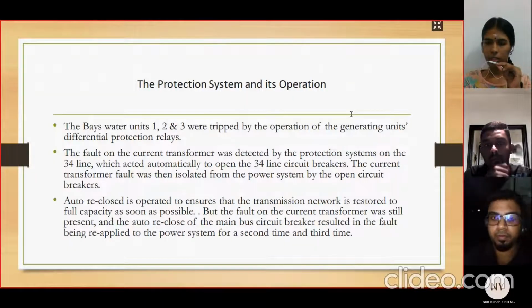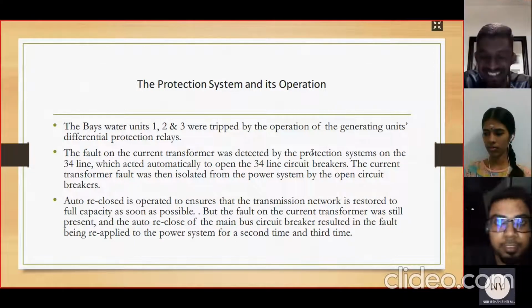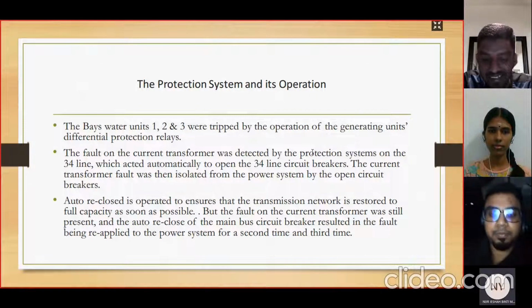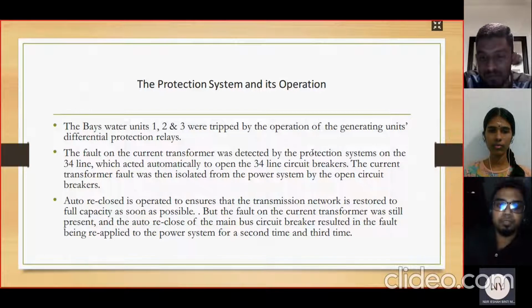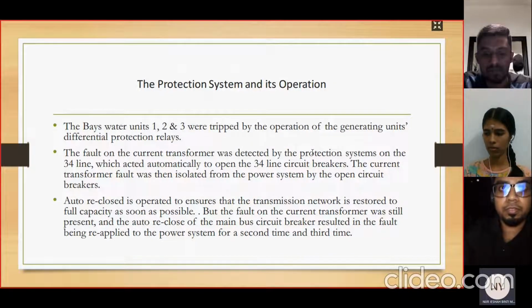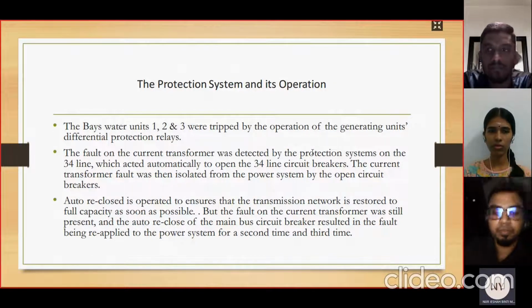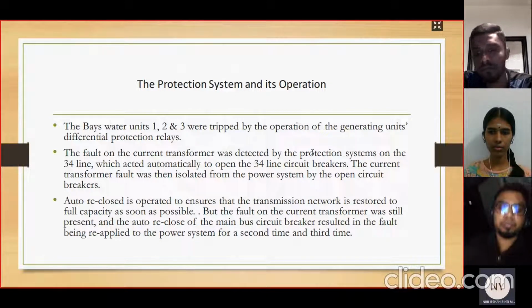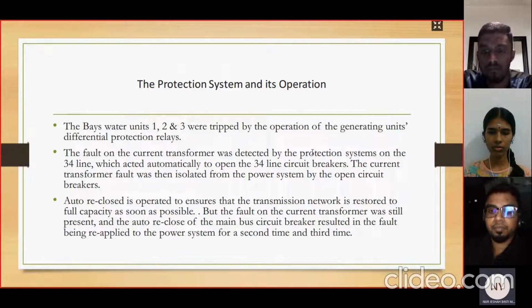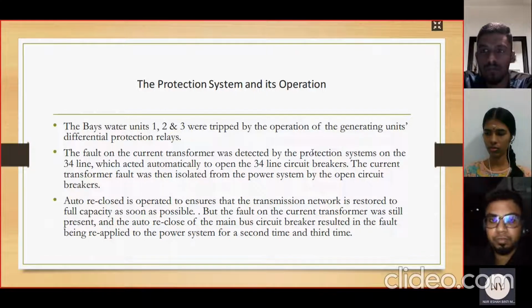Next slide. This is the protection system in this incident and how it operates. Bayswater units 1, 2, and 3 were tripped by the operation of the generating unit differential protection relays. The fault on the current transformer was detected by the protection system on the 34 line, which acted automatically to open the 34 line circuit breaker. The current transformer fault was then isolated from the power system by the open circuit breaker.